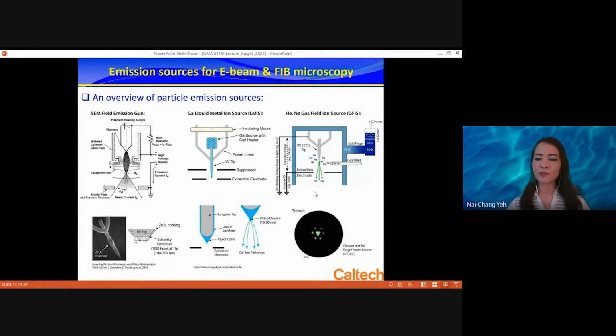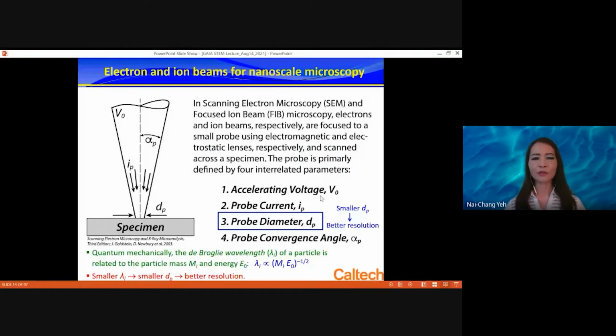Once these particles are extracted, you use different techniques to focus the beams into small dimensions. In scanning electron microscopy, SEM, or focused ion beam microscopy, FIB, electrons and ion beams respectively are focused into a small probe so you can get high resolution, allowing you to image or fabricate small structures. For electrons, you use electromagnetic fields to focus the beam. For ions, you use electrostatic 'lenses' to focus the beams, similar to optical lenses for photons. The principles are similar if you think in terms of particle-wave duality—only the focusing mechanism differs.